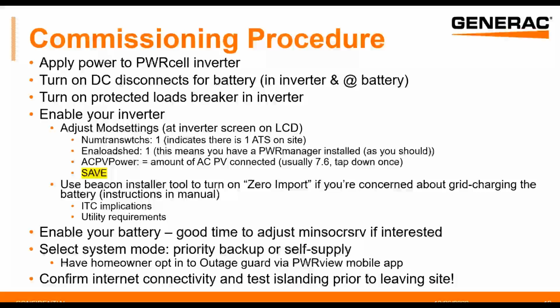So from a commissioning perspective, this probably looks like a lot on the screen. The reality is at my inverter, I could do all of this in like 3 to 4 minutes. It's quite fast. So it's very similar to commissioning a standard power cell system. It's only going to take a few minutes. You're going to apply power to the inverter, turn on your DC disconnects inside the inverter, turn on your protected loads breaker in the inverter, and then you're going to enable your inverter at the screen on the inverter, which will bring up the DC bus to 380 volts.